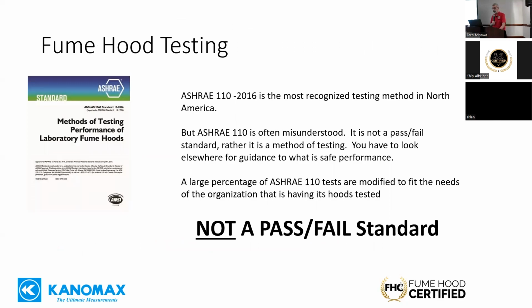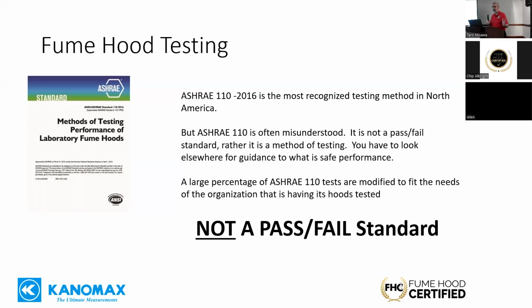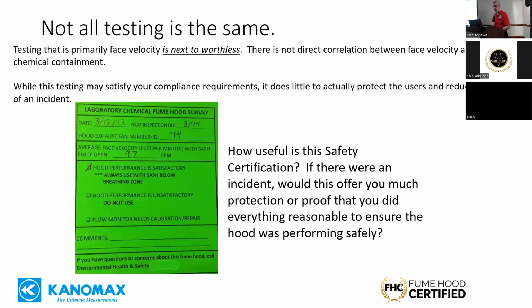In the United States, ASHRAE 110 is the most notable testing standard, but it's often misunderstood. People say your hood has to pass ASHRAE 110, but ASHRAE 110 is not a pass-fail standard—it's only a methodology. So you have to go somewhere else to find out what's safe. Most commonly here in the US, we use the guidance in ANSI Z9.5, which is the most common standard for determining what amount of leakage is acceptable.